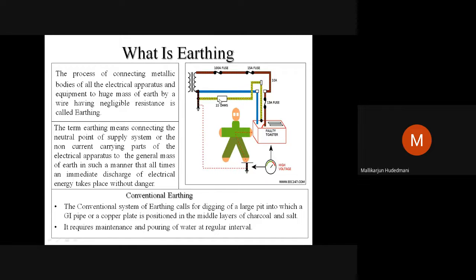If this wire is not there, just imagine, the earth wire is not at all there. Now I am talking about the connector of a mixer grinder, a television or any gadget. Often, if there is no 3-pin socket in the house, what do we do? We modify the connection to 2-pin. One of the bigger pins we break down and we make only 2-pin. That is what we call danger. When the third pin, which is the safety pin called earth, you eliminate and you touch the gadget, the wire which would have carried the faulty current is no more there. Then your body becomes a third wire for that. So the fault current rushes down to the body. That is why earthing must be there.